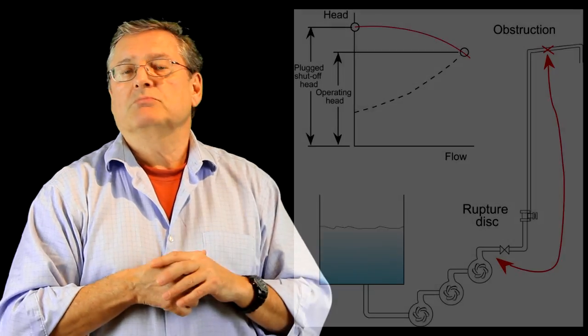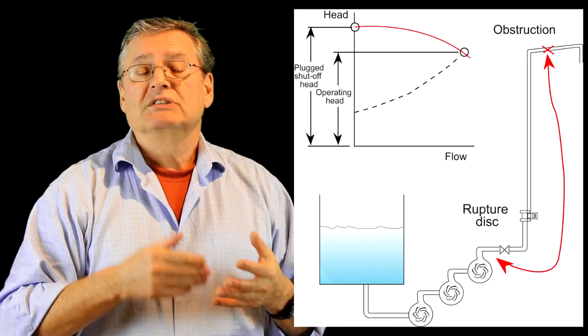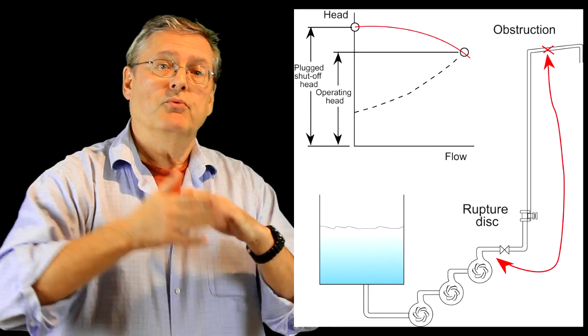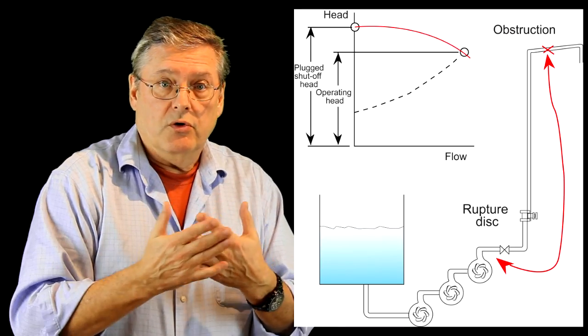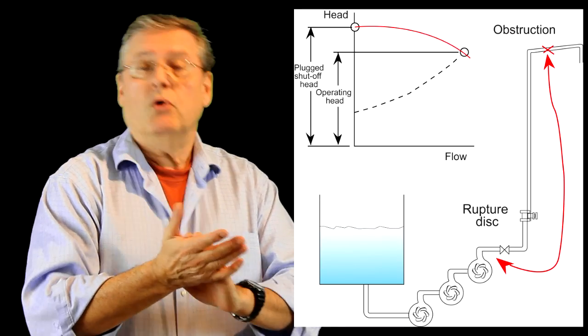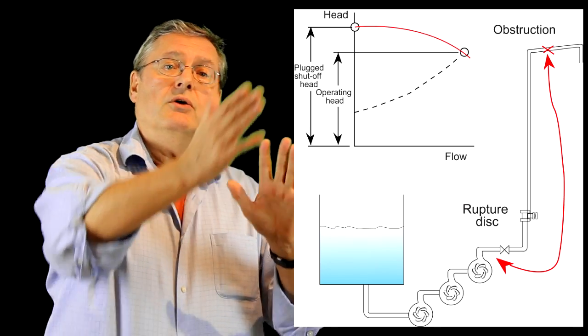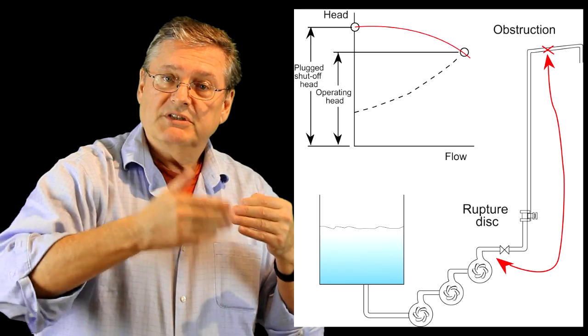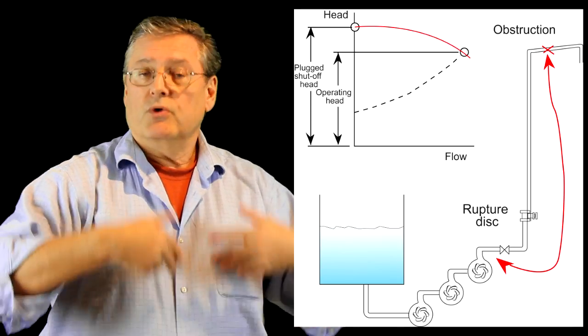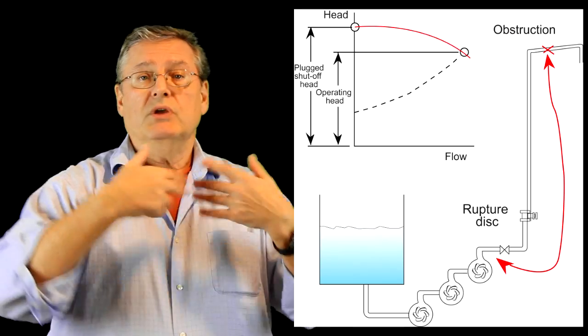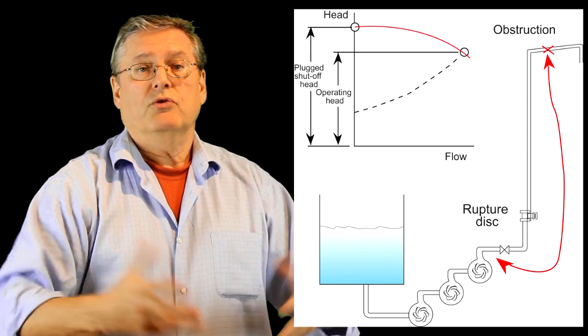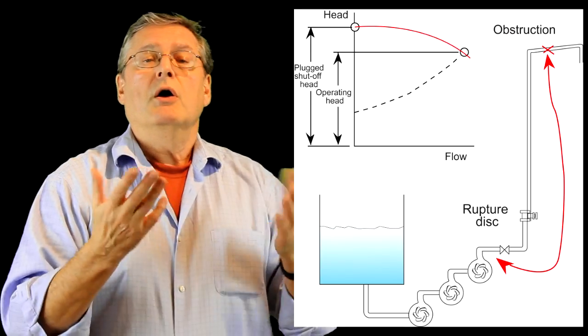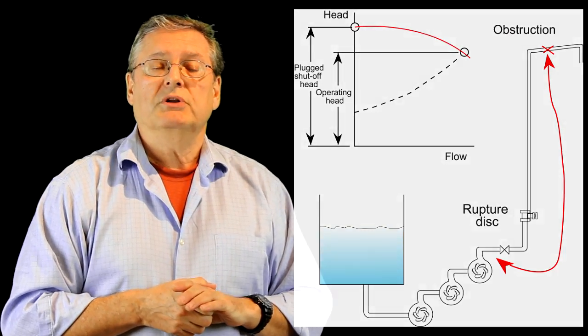In cases such as mining where we have several stages, if there's an obstruction in the line the pump will have no flow or zero flow. When there's no flow in the centrifugal pump, the head goes up and the pressure goes up. If you have several pumps in series that's cumulative, so three pumps means the pressure will go three times as high and you could damage the equipment. It's common practice to put in a rupture disc.